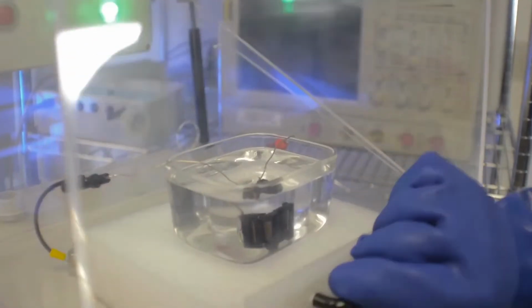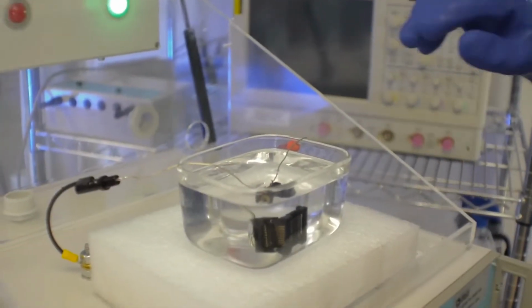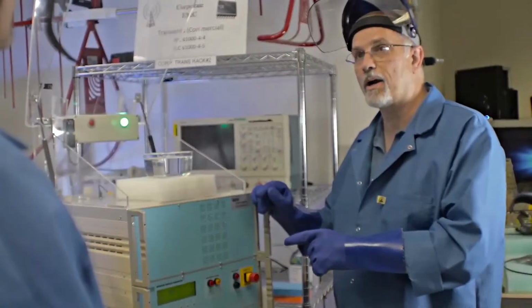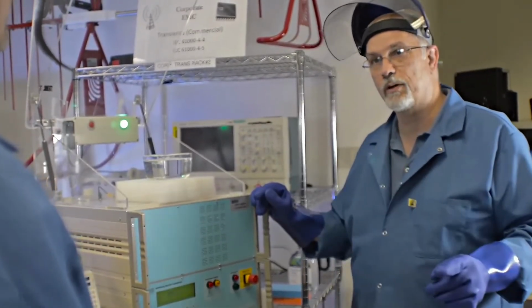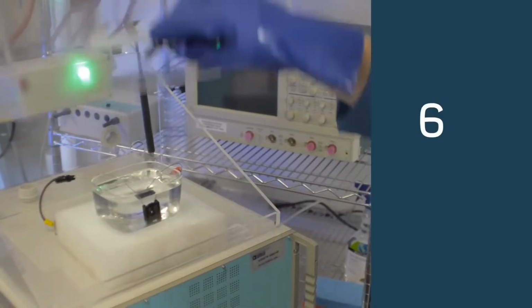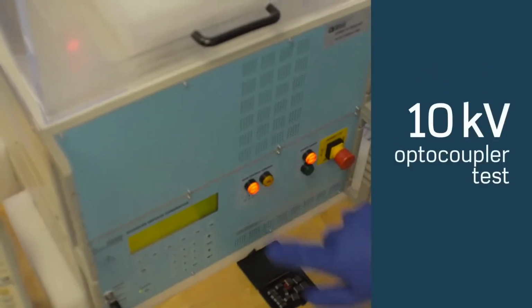Is this the machine that does the 1.2 by 50 microsecond pulse that the agencies use? It's exactly the same. VDE requires a 10 kV pulse as proof of reinforced insulation, so we're going to start with a 10 kV pulse.